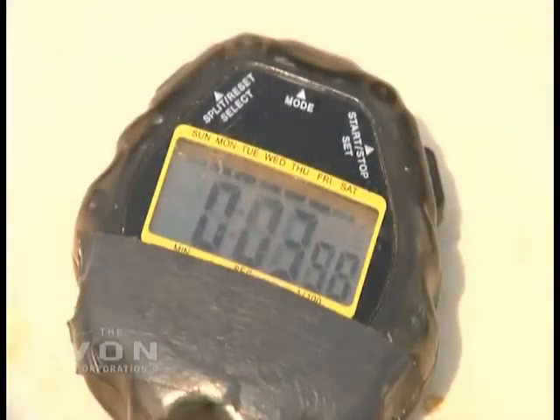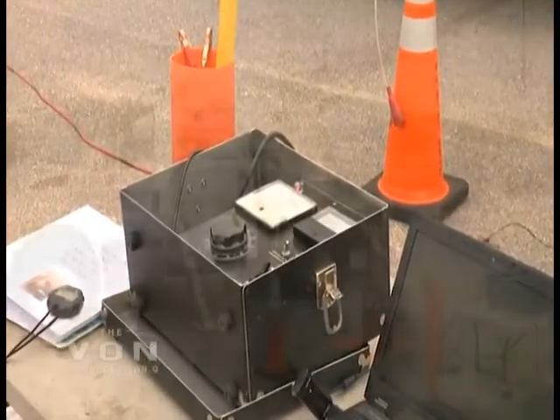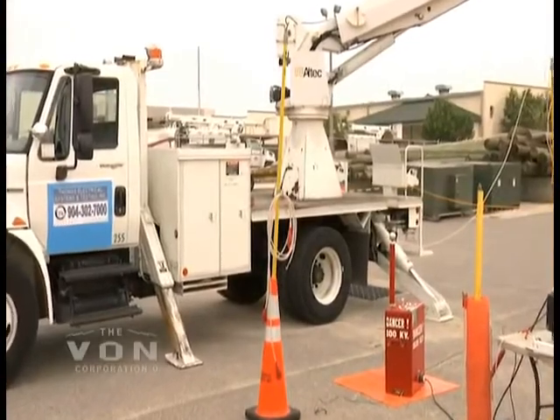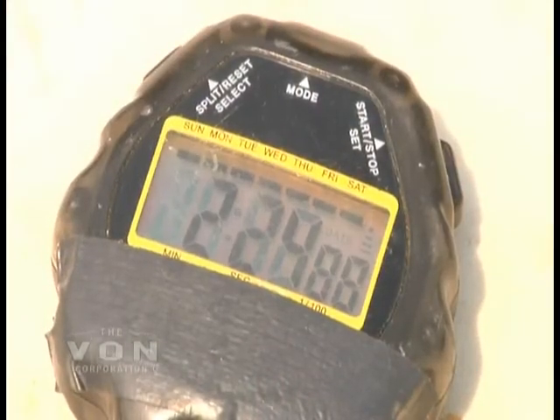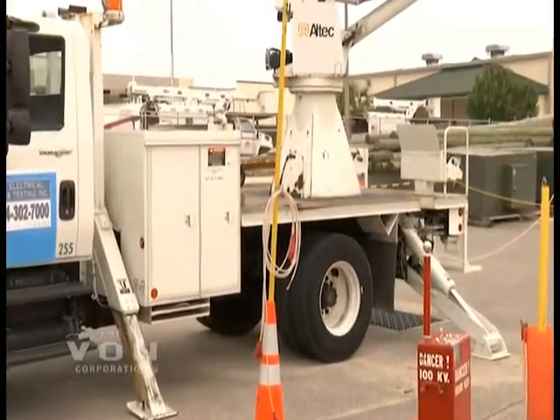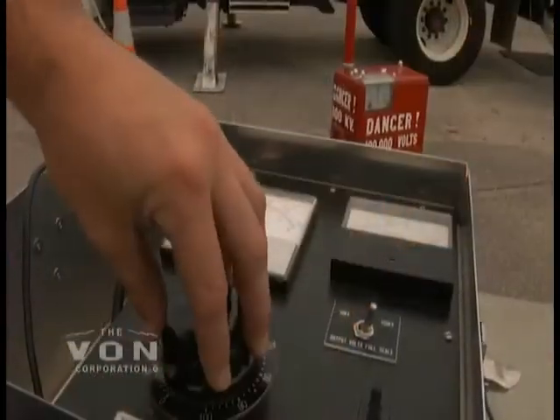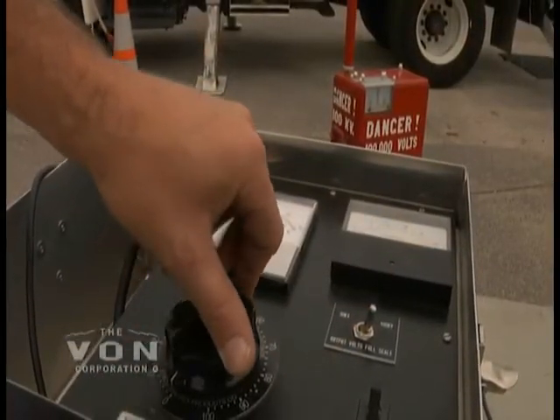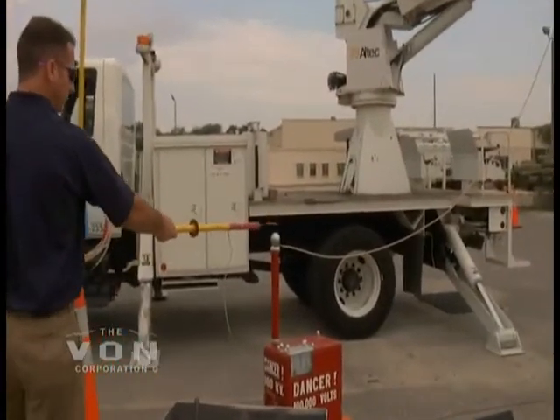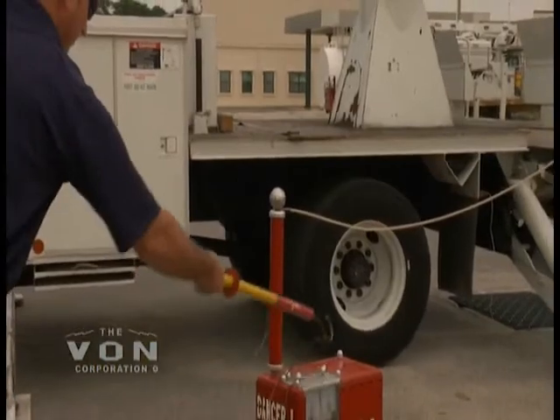The Von unit takes very little power. You can actually hook it up to a converter on your vehicle and operate the machine off of a converter, so you don't have to carry a generator with you to operate this unit. The test is now run. We are grounding the unit. We have used our ground resistor stick to bleed the unit off. Then we are placing our hard ground on, and the unit is now grounded so that we can operate the truck.